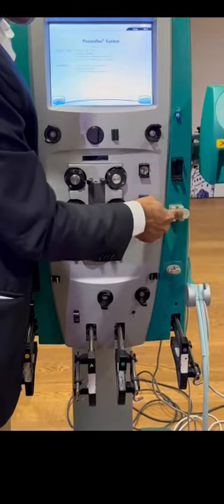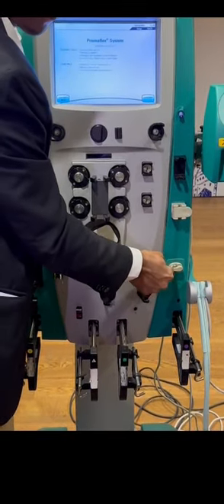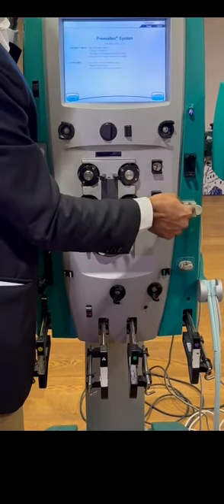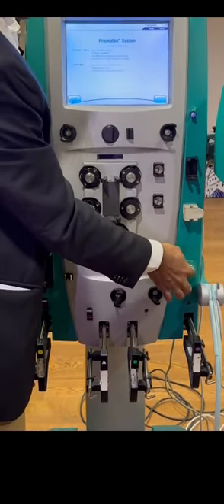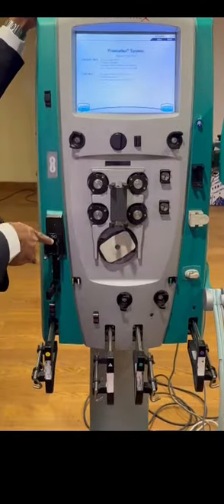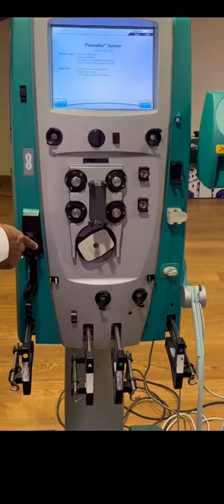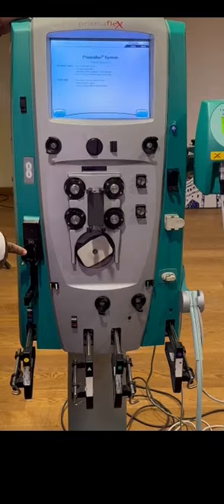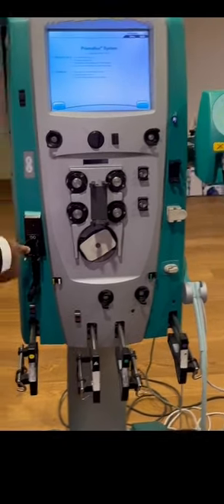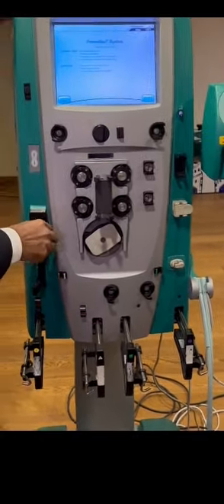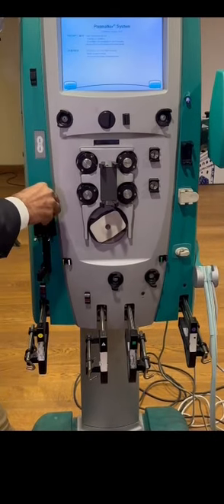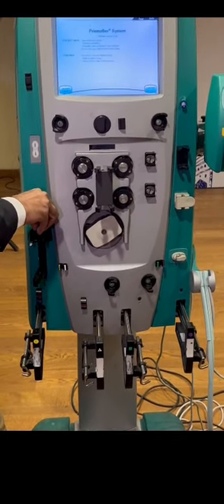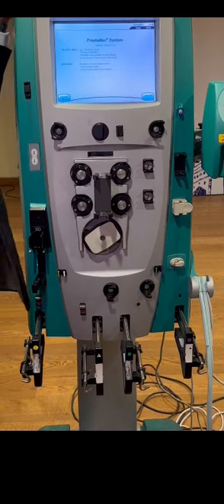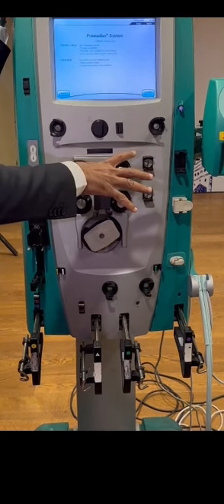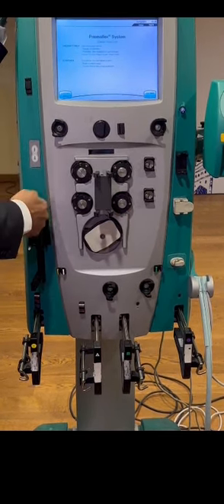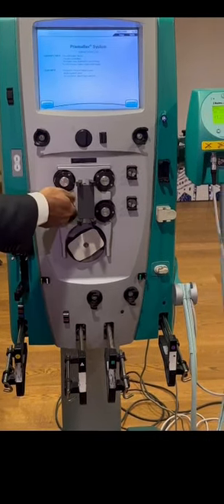Okay, this is the air detector. So this is the clamp. Okay, if any air is detected, we need to stop the further flow. So we have a clamp. Then this is the syringe pump. Okay, so this we can use for the heparin infusion. At the time of citrate anticoagulation, this will be converted into a calcium replacement pump. Okay, if we are using this pump for the calcium replacement, this line will go directly to the patient, not to the circuit. Okay, for the calcium. If it is heparin, this will go to the circuit.